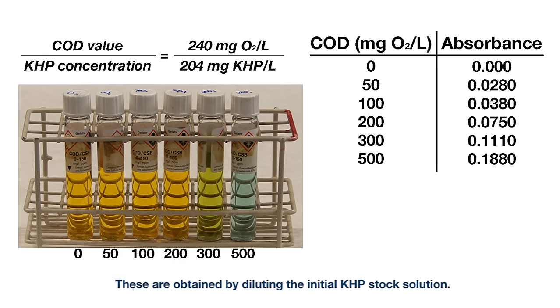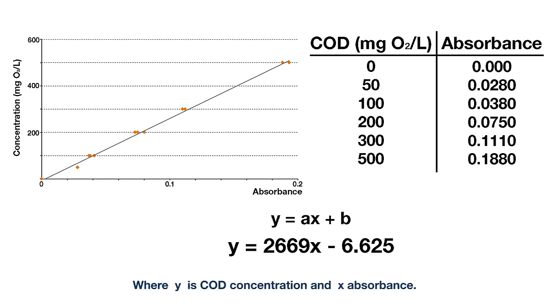These are obtained by diluting the initial potassium hydrogen phthalate stock solution. Once that's done, the absorbance of all standards is read in the spectrophotometer, and the equation fit, where Y is COD concentration and X is absorbance.